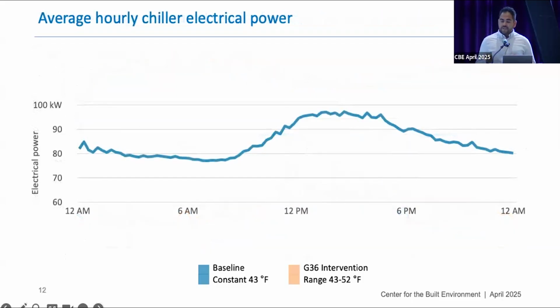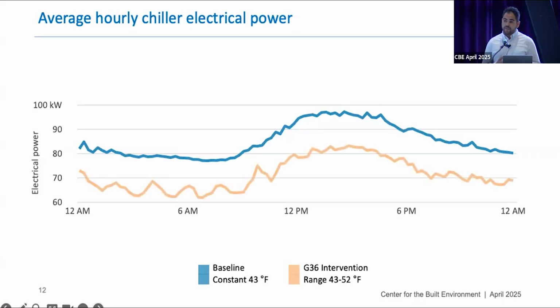So how do these differences affect the electrical consumption for the chiller? We see that for the baseline operation, the power consumption ranges from 70 kilowatts to almost 100 kilowatts during peak conditions. And for the intervention, we observed that there was a reduction of 10 kilowatts, which is pretty substantial for a chiller water plant that is operating 24/7 due to the nanofab. So we were able to save some energy through this.